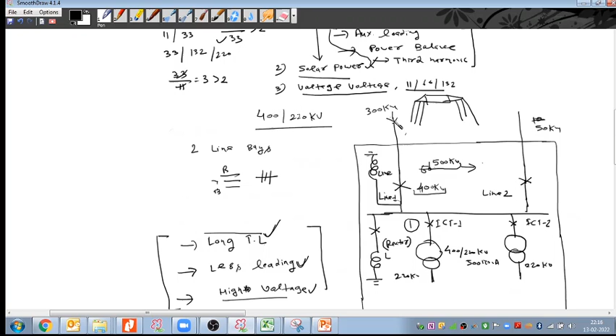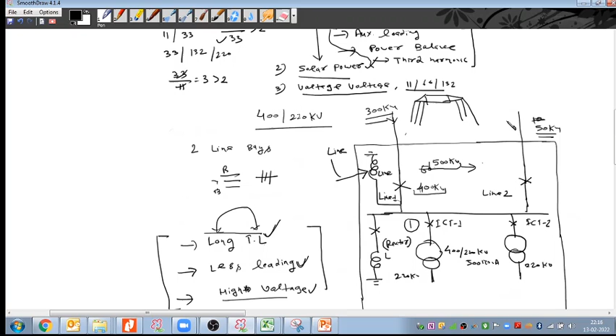Because this is the short transmission line, and for the Ferranti effect, this should be the long transmission line. So this is the long transmission line. If there is only one very long transmission line injecting the reactive power, then in place of connecting this reactor on the bus, I can connect this reactor in shunt with this line. In that case I will go with the line reactor. And suppose we have two or three or four lines, and both are very long transmission lines, around 300 or 400 kilometers. Then in place of putting two line reactors, we can put one shunt reactor on the bus. Shivam, I hope the selection is clear, when I go to the line reactor and when I go to the bus reactor.